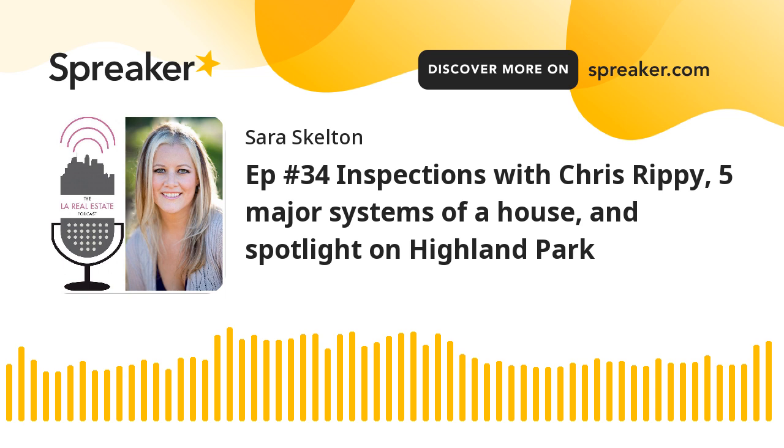And I've seen that lots, with Romex wired on the outside of the building, just strung around, all sorts of stuff like that. The other thing to keep in mind is just age. I think Chris touched on the knob and tube, but what he didn't get into is that they didn't have grounded outlets until I think the early 70s, late 60s, early 70s. So sometimes you'll go into these houses and you'll just see the two slats. That happens a lot, yeah. And you won't see the little dot. The third prong, the place to put the prong.